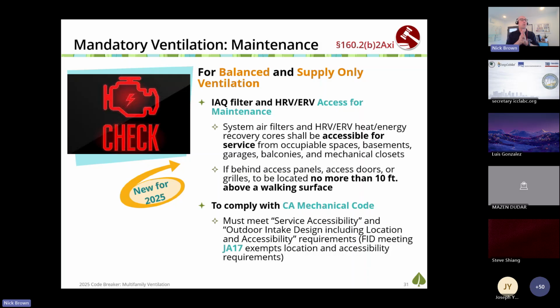Now, if we have a balanced or supply ventilation system, we also have to have those filters and heat recovery cores, if applicable, accessible for maintenance. Otherwise, the filters are going to bridge over and the systems are not going to operate as intended. And so this is new for 2025, that this accessibility requirement is a mandatory requirement. No more than 10 feet above a walking surface. So think about your multifamily buildings. How are they going to provide in a 3 and 4 and 5-story multifamily building for accessibility of these filters? They really need to think about that. Can't be bolted to the exterior of the building, right? So that's going to challenge designers to figure out the location of their ventilation fans.